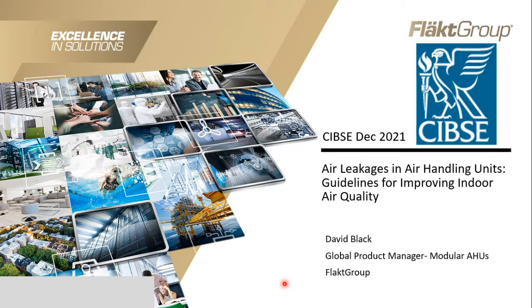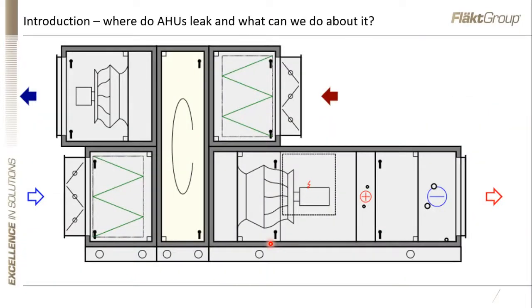You're fine. The subject of my presentation is air leakages in air handling units, guidelines and indeed guidance for improving the indoor air quality. And it follows on pretty much from what Peter's been saying. It's all very well to have very efficient filters in your air handling units, but if the air handling unit itself leaks, then we've almost certainly got a bit of a problem with the indoor air quality. There we go. So where do air handling units leak?